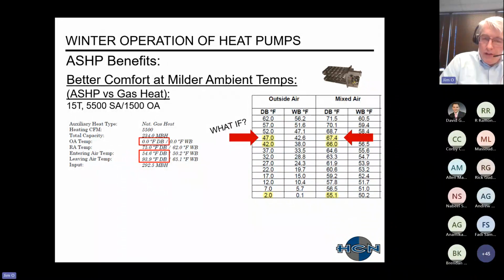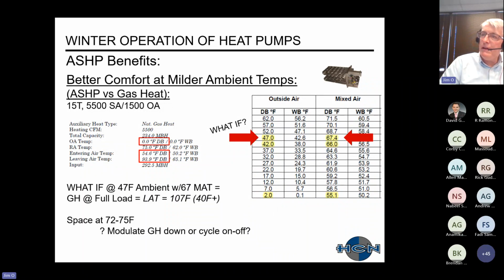Now, that's when you design your heating for your worst conditions at your design temperatures. But what happens when your outside air temperature is at more common outdoor temperatures? In this example, I just used 42 and 47 to highlight that my mixed air changed from 55 up to 67. So if I went back to that gas heater, which is sized for about a 40-degree temperature rise, I'm going to have a leaving air temperature of approximately over 100. If my space is at 72 or 75, that 100-degree air is obviously going to be way too warm. Also, if my ambient temperature is at 47 or 42, I don't really have that great of a heating requirement. So the question is, is a gas heater going to be able to turn down properly, or is it going to cycle on and off, which you don't want to do.